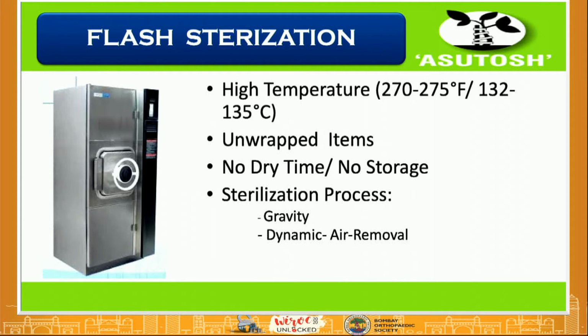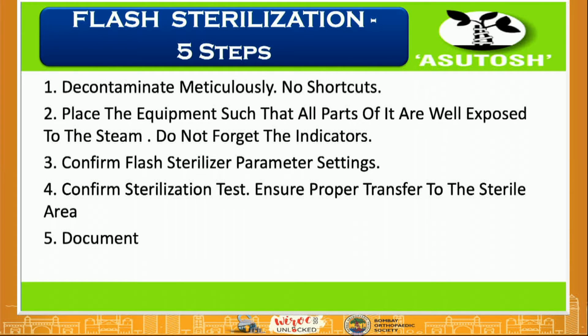The flash sterilization, the word is so attractive that everyone just says flash karo, usko flash karo. But always remember that there are no shortcuts in a flash sterilization. The first thing is one has to decontaminate properly. All the sides of the equipment should be exposed to the steam. Get your parameters right. Put your indicators. Confirm your parameter settings. After you have removed the equipment from the flash, you should look at the indicator that the sterilization has taken place.